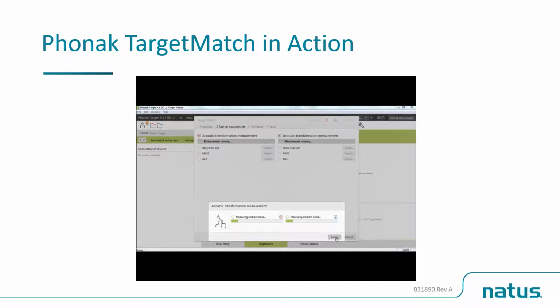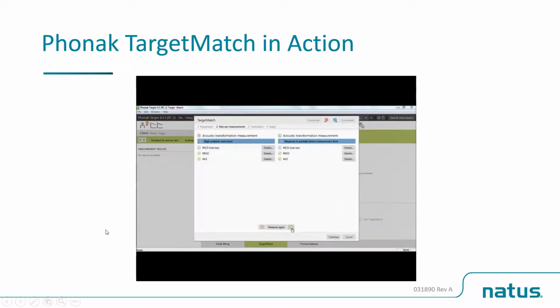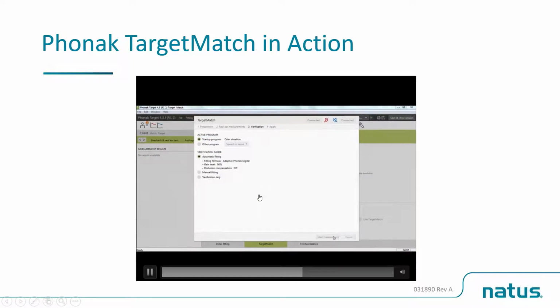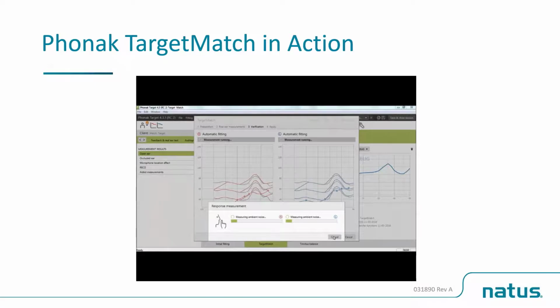Now, as you see, the first thing it's going to do is run those acoustic transformations. You're going to see that it's constantly remeasuring the ambient noise throughout this process, and the reason is we really want to make sure the results are accurate. As it's finishing up, what you're looking for is to see if you've got these green check marks. If you see any exclamation marks, you can get more detail. Sometimes, if you open up the details, you will see at 250 hertz there might be a little bit of ambient noise, but typically it's only about 3 to 4 dB, and it's not enough to impact the fitting. If it was too significant, it wouldn't allow us to advance, and the continue button wouldn't be there.